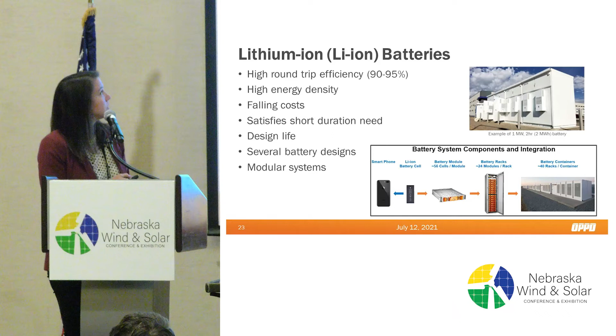Okay, a couple things to talk about when we look at designing and sizing the battery. You have the capacity. This is the measure of energy stored in the battery, the megawatts that you hear about. For this project, as I mentioned, this was defined at 1 megawatt per the grant. Duration is the runtime of a battery on full charge in hours. So this is the hours component that you'll hear referred to. We looked at 2-hour and 4-hour, and I'll talk a little bit about the differences shortly. But this is an important piece for how you're using the battery, how much duration you want it to have. And then finally, the cycle. This is a full charge or a full discharge, or the equivalent of the capacity. So this is something that we had to define up front.